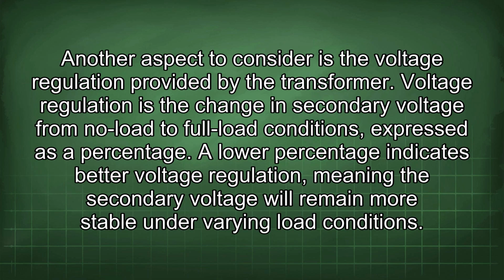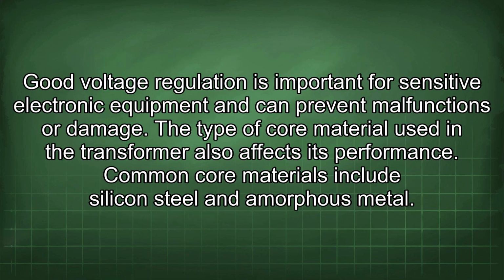Another aspect to consider is the voltage regulation provided by the transformer. Voltage regulation is the change in secondary voltage from no load to full load conditions expressed as a percentage. A lower percentage indicates better voltage regulation, meaning the secondary voltage will remain more stable under varying load conditions. Good voltage regulation is important for sensitive electronic equipment and can prevent malfunctions or damage.